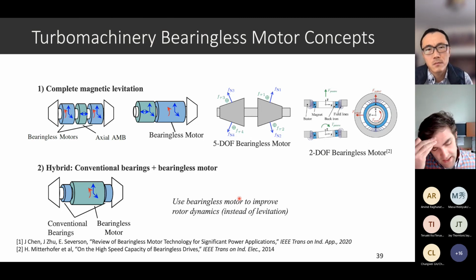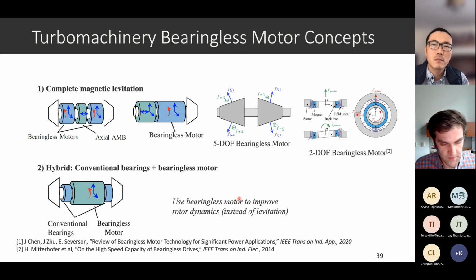For magnetic bearings, if you do a side-by-side comparison study of any bearing technology with a magnetic bearing, you pretty much always find the magnetic bearing has less losses. For example, there are lots of case studies now for wastewater aeration equipment using magnetic bearings in place of oiled journal bearings. Usually the oiled journal bearings, because of the large axial loads, may have upwards of 2 to 5% of the motor's power rating appearing as losses, whereas magnetic bearings are typically around 0.1 to 0.2% of the motor's power rating in losses. So it's quite a sizable reduction.